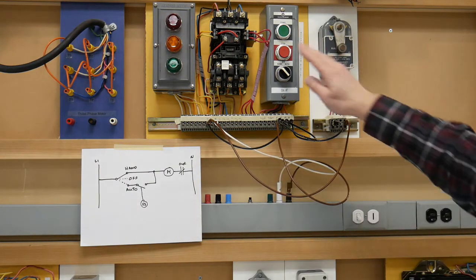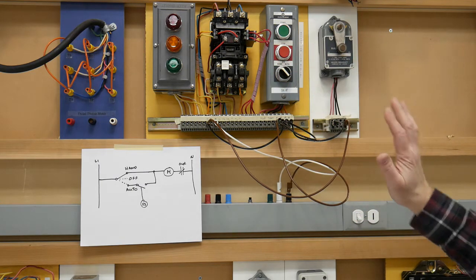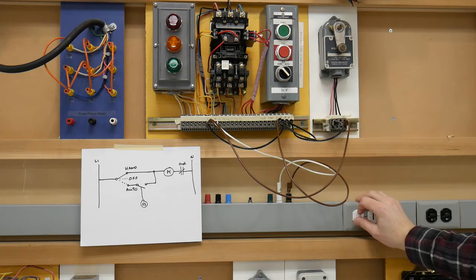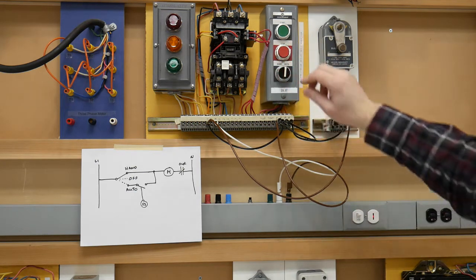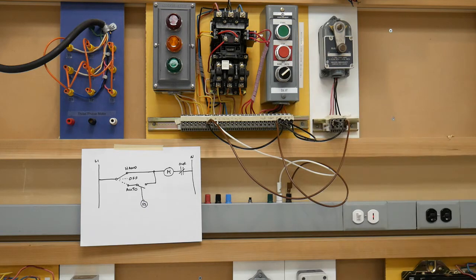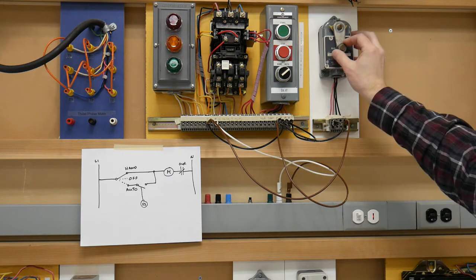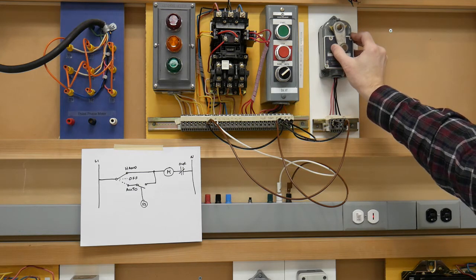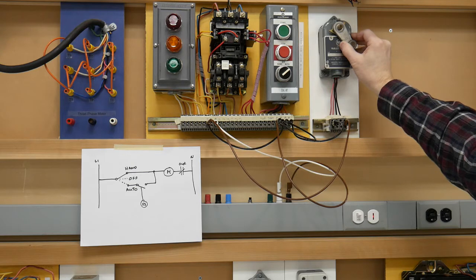So if I'm in the hand position the minute I power up I should be feeding the coil, so don't be alarmed if this thing automatically starts to run, which it does. I'll turn it to off, it stops. We'll go to auto, nothing is happening. And let's pretend this limit switch is the float, so the liquid is slowly filling up and then it hits the point where it's actually going to overflow, now we're running again. So we know that works.